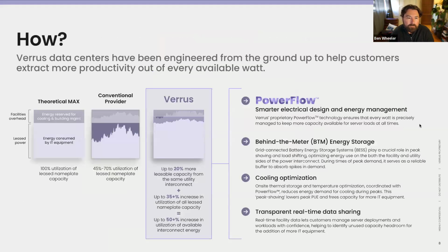And how do we do that? This is a little more detailed, but I'll give an overview. If you look at the box on the left where it says theoretical max, that total box represents a utility interconnect - the amount of energy totally possible to get out of the interconnect at a given data center site. There's a certain amount of overhead reserved for cooling that has to be kept for the peak, hottest, most humid day of the year. But most of the year, it's not really used very much. And then the remaining is what's able to be leased to customers.